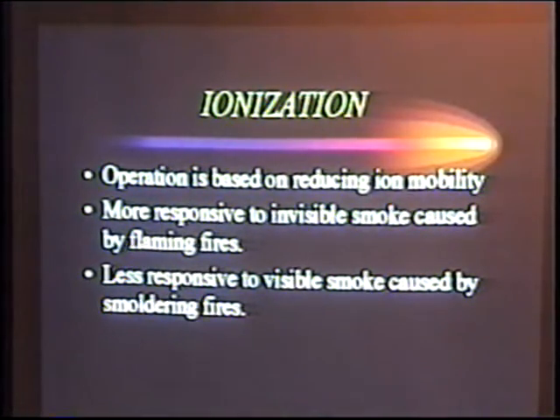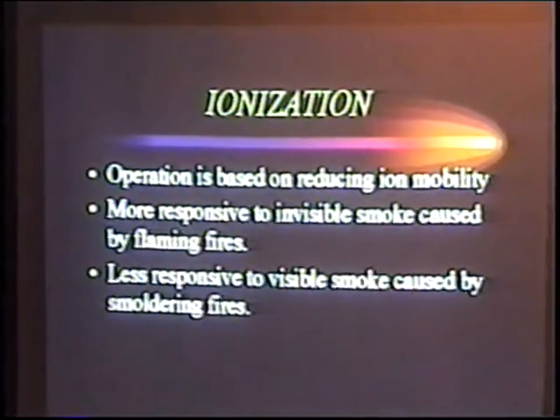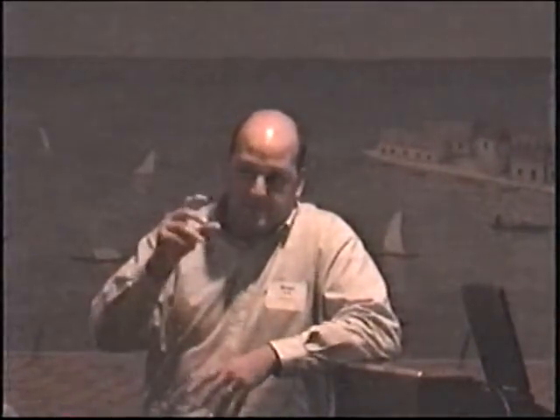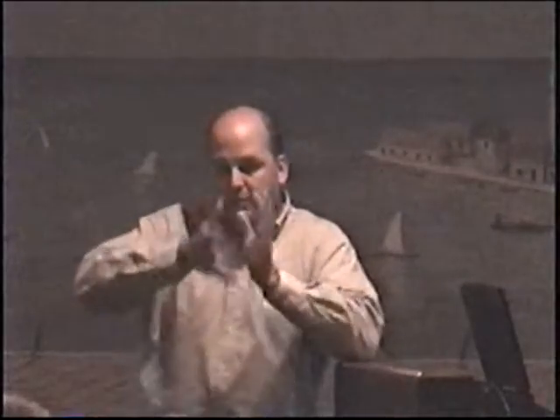Ionization detectors, their operation is based on reducing ion mobility, or current change. Inside the detector, we have two chambers. In one of the chambers, there's usually a small amount of radioactive material. That radioactive material makes ions in the air inside the chamber. Those ions are all moving around, creating this current draw. As smoke particles come into the chamber, they absorb the ions.